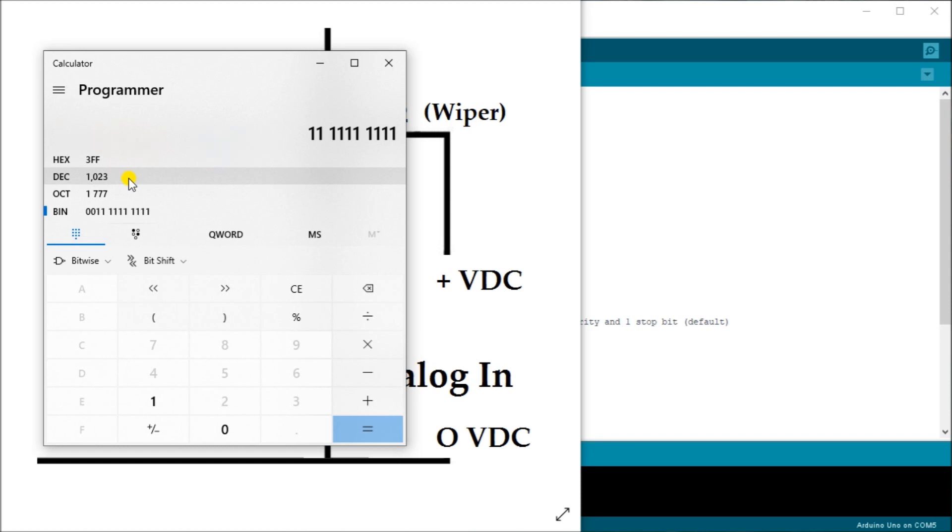So decimal, you'll notice is 1023. So if we count zero as being also a place, the resolution is going to be 1024. So what it does is takes that zero to five volt signal, and converts it into 1024 equal segments along that resolution, giving us our 10 bit resolution. So the higher bit count, the higher that number is, the more resolution we get per voltage level that we're reading into our controller.